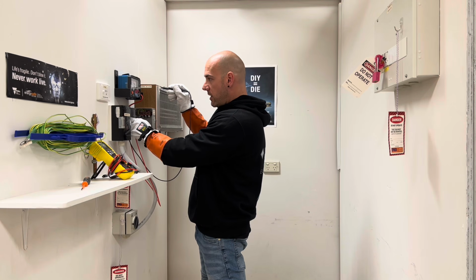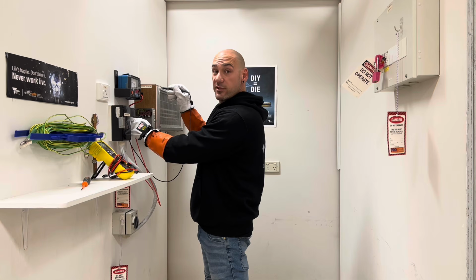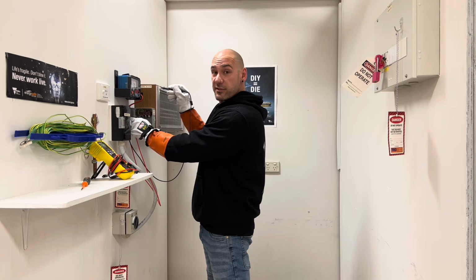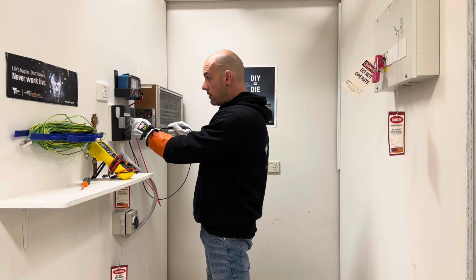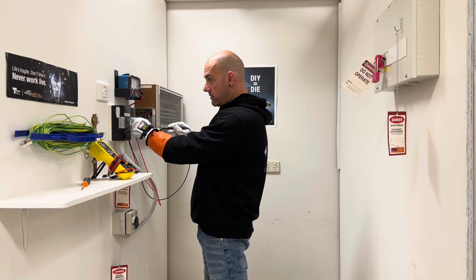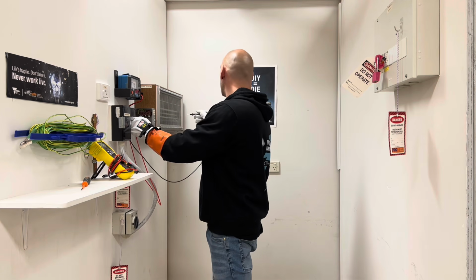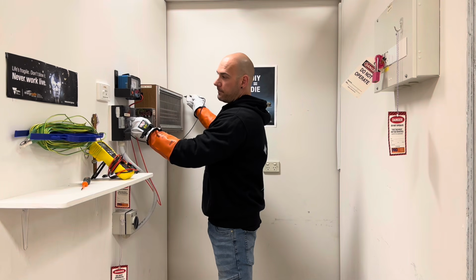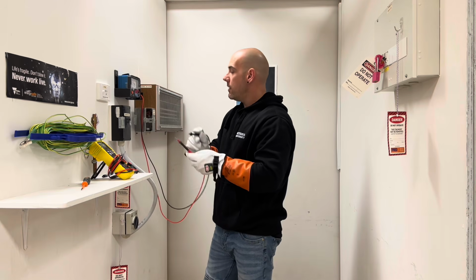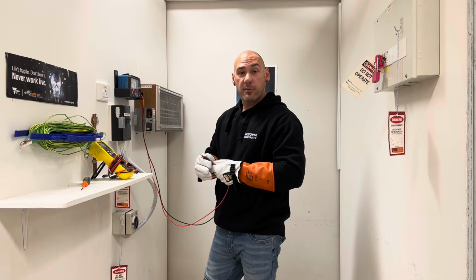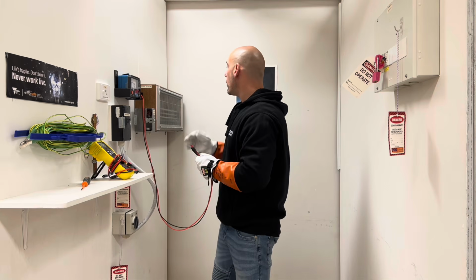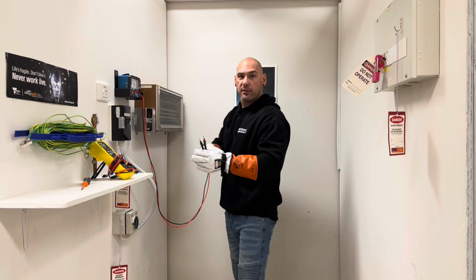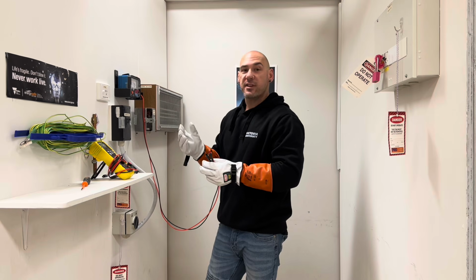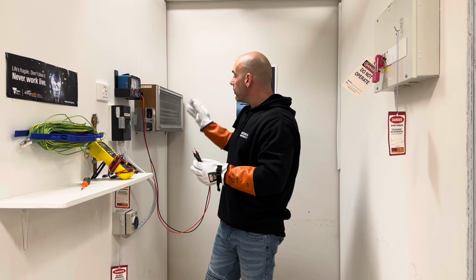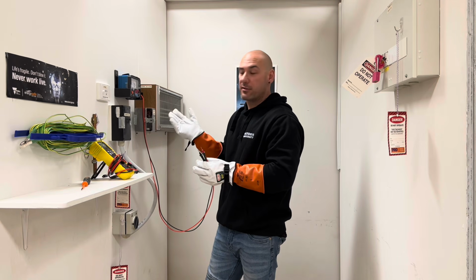And right now we're reading 0.1 of an ohm, which is a good low resistance. Check a second spot, it's a little bit less, and one more. Okay, we test our tester, and I'm pretty happy with that earth. Now it's time to do an IR test. We need to turn the heater on to its maximum. The reason for this is we need to make sure that all the wiring inside the heater will be activated.